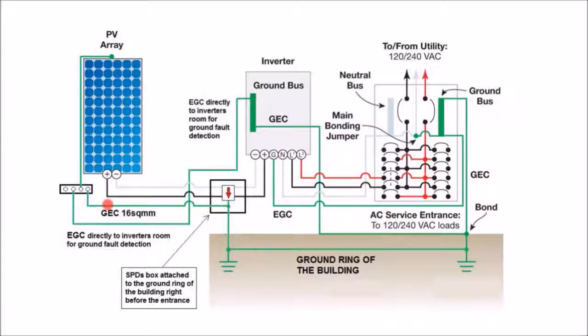The neutral wire is at that point used as a signal between the rapid shutdown box and the inverter. So when the inverter detects a grid failure, it'll send a signal through the otherwise unused neutral wire up to the rooftop where the combiner box is. Then we trace back this neutral, and maybe there's a transformer inside the inverter or not. If there is, regardless, we're sharing the neutral with the utility neutral.